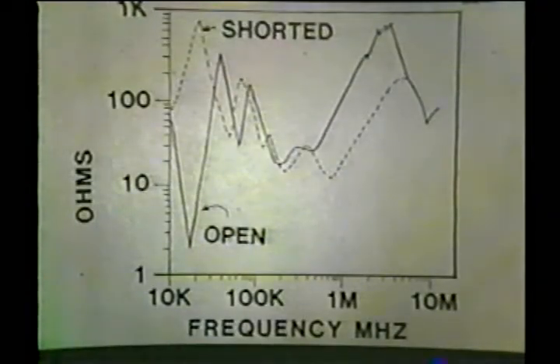Since EMI was tunable, I was quite curious whether the resonant frequencies inherent to a machine would tell me where I could find EMI. If you look at the impedance of one terminal of the machine, in this case a 140 MVA turbine generator, you can see that the input impedance is quite dependent not only on frequency, but on whether the opposite end of that circuit was open or shorted.